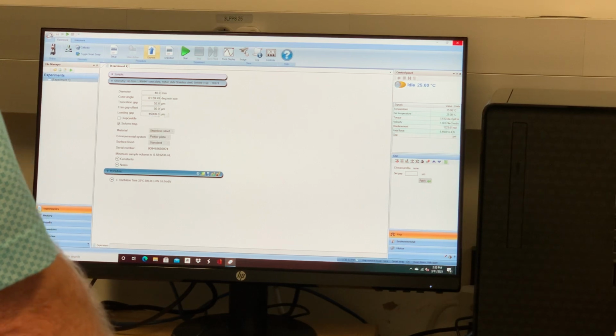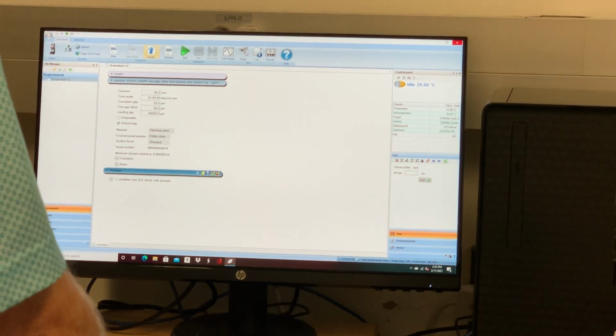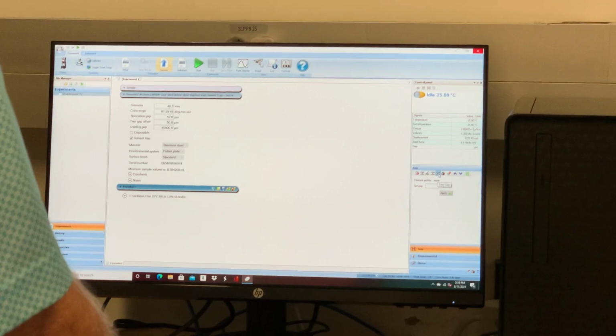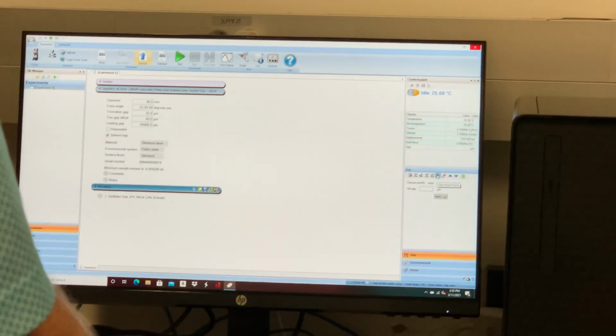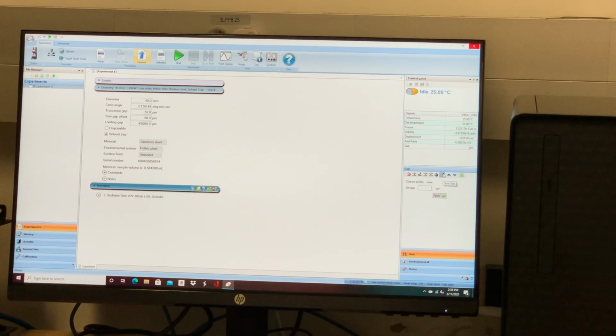Raise the loading gap. So the loading gap is right here, 45 millimeters. That's the gap you're going to load your sample in, okay? So you can change that. If you find it's not high enough, you can change it to whatever. This is an important one, zero gap. That's what we're going to do. Zero the axial force, so how much force is on the sample. You can tare the gap, so you can do a manual gap if you wanted to. And then we have up and down.